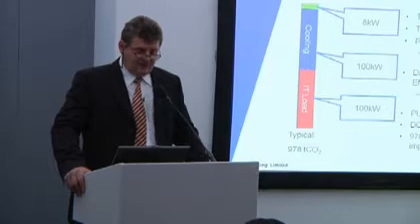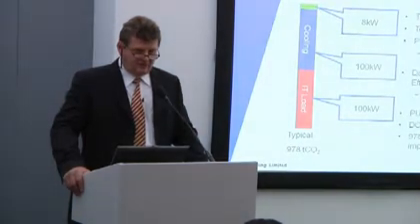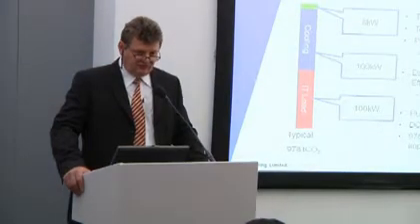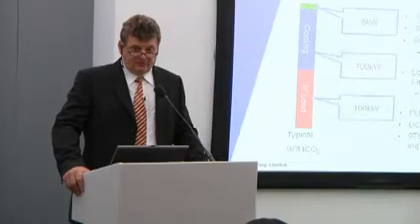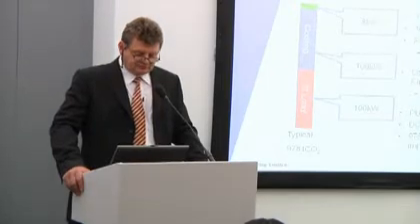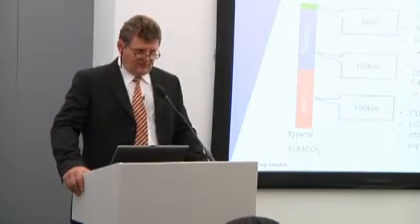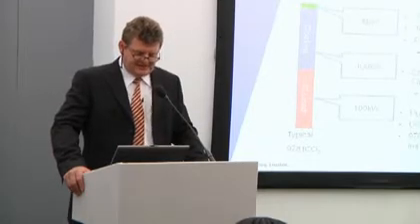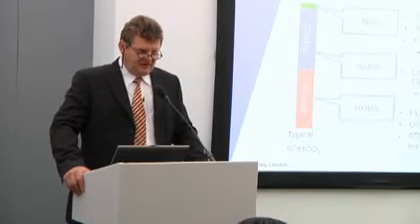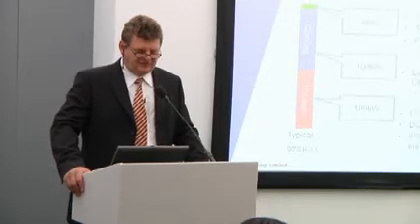Now, this is obviously an incredible cost, both in terms of the electricity usage and its carbon footprint, and also the consumption of the available power, where many sites have run out of available power. So, we look at this ratio called a PUE. You'll also come across another expression called a DCIE, a data center infrastructure efficiency, which is purely the inverse of it. It's like a percentage efficiency.